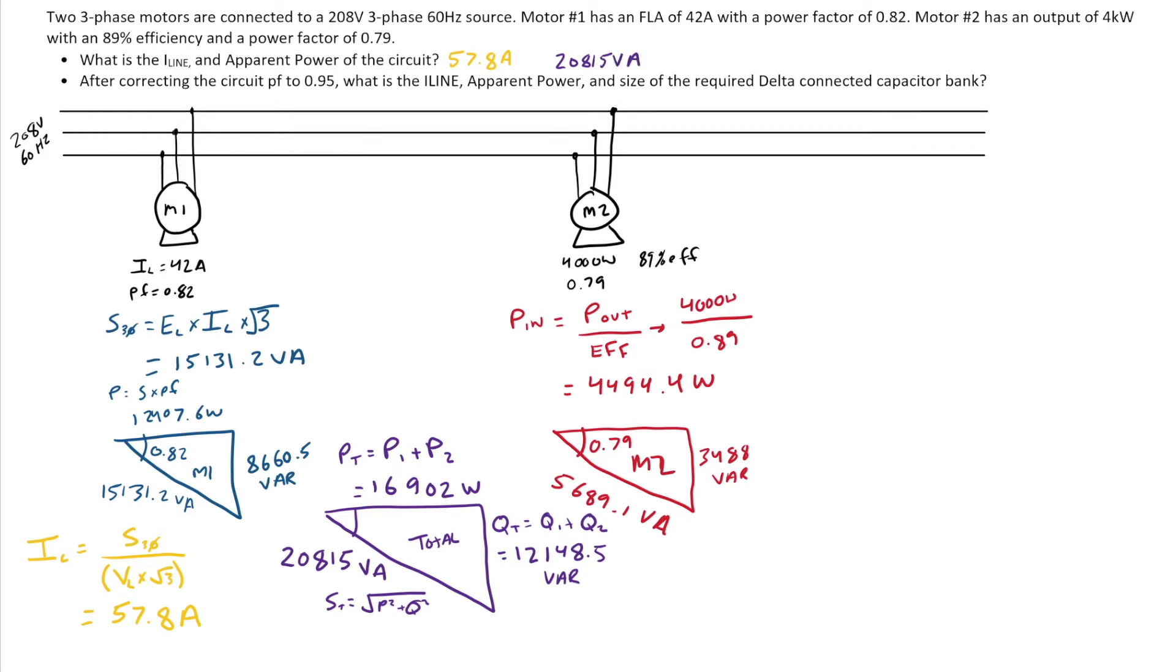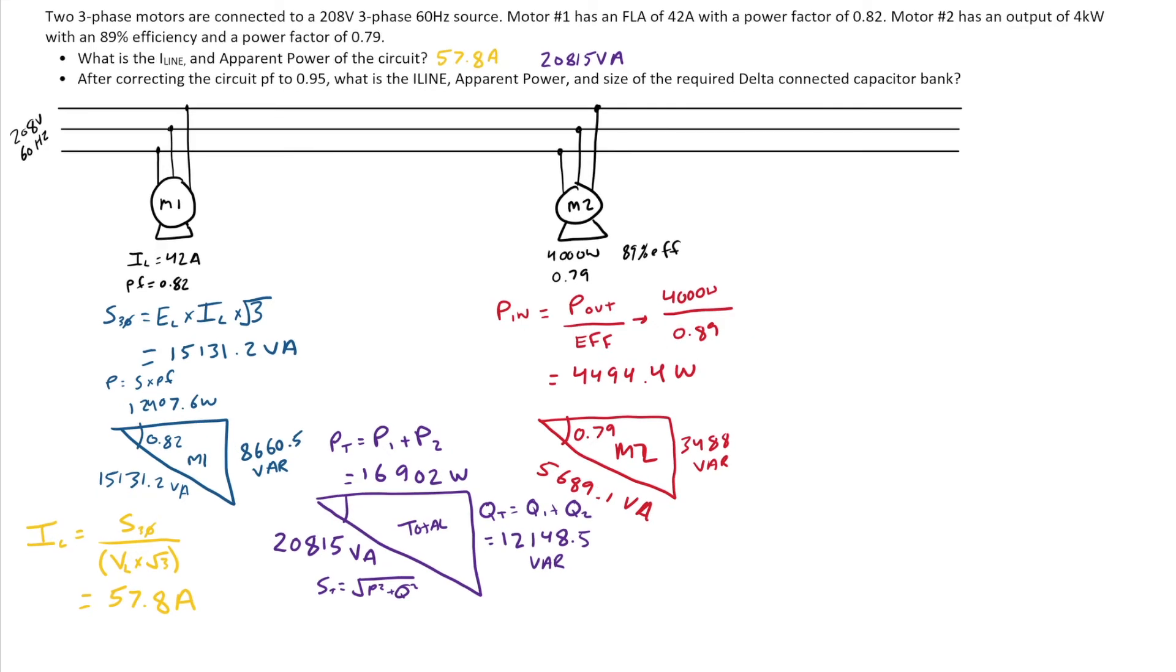Now, next up, it is asking us to power factor correct the circuit to 0.95. Now, we've got to remember the goal of power factor correction is always to reduce the incoming line current. The goal is to reduce the current leaving my source. It's not going to change the current going to each motor. Nothing about the motors will change.